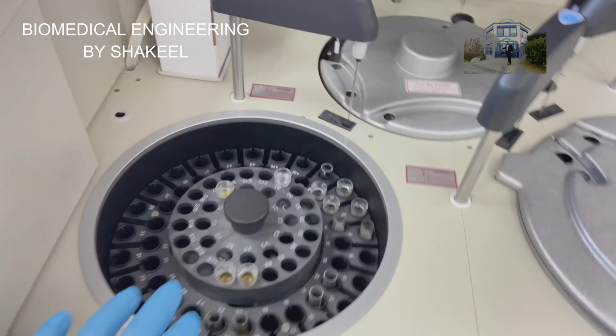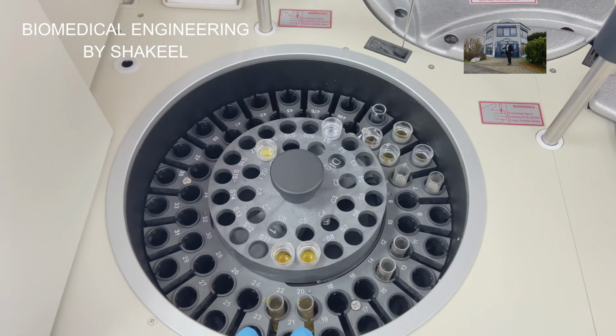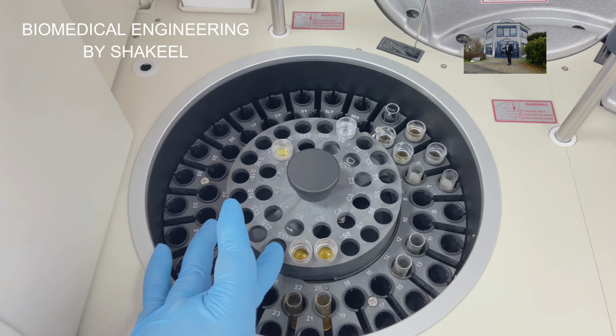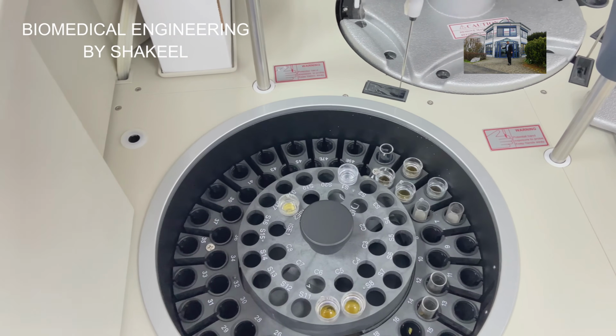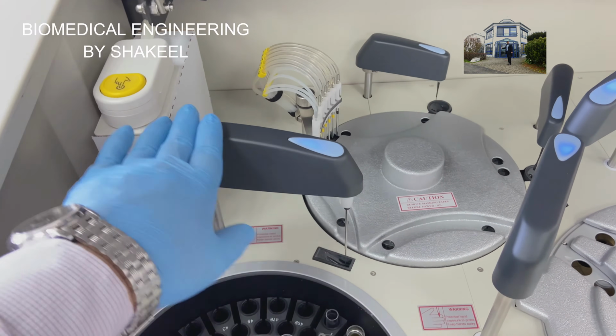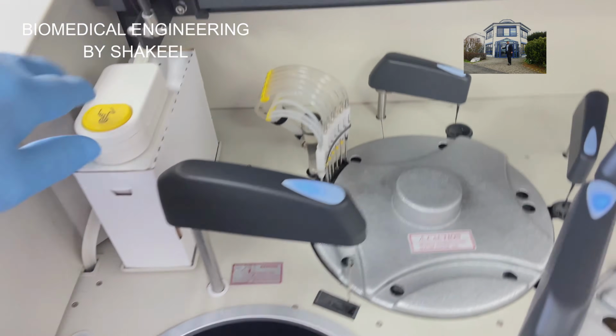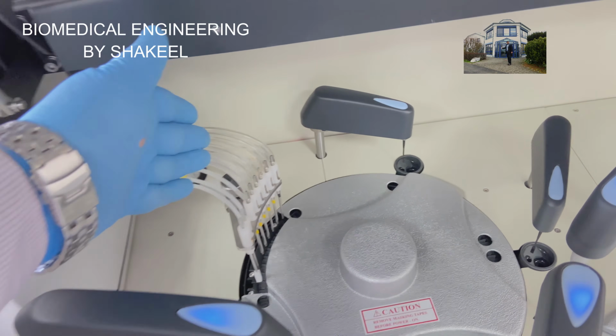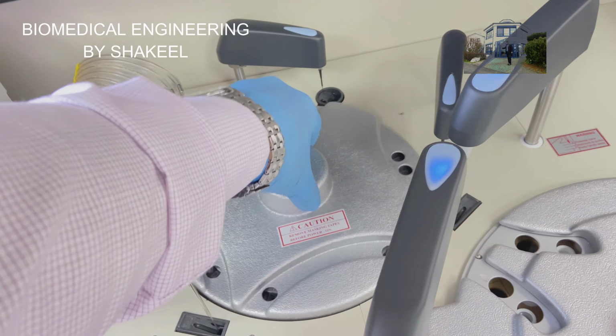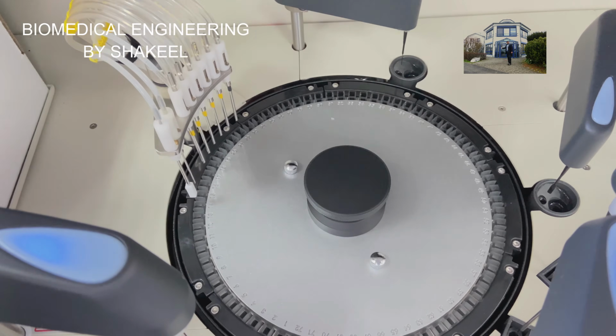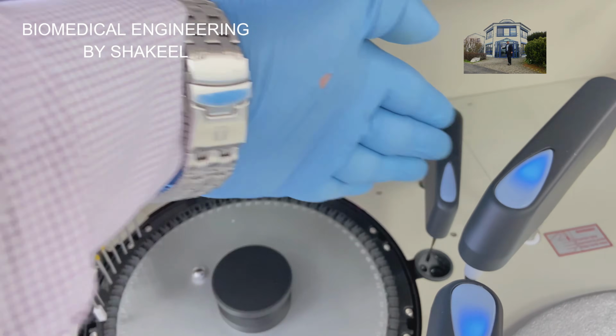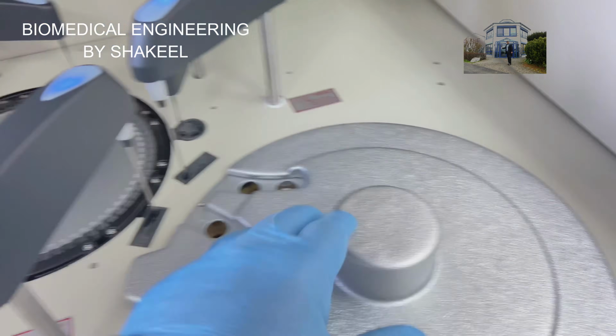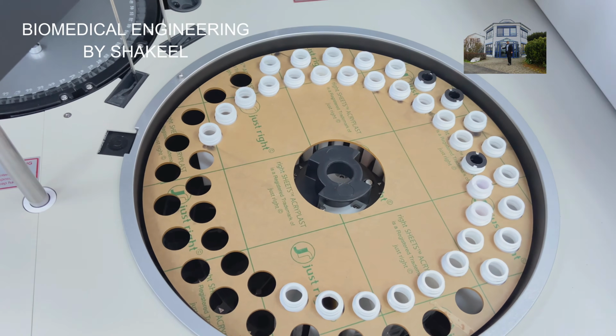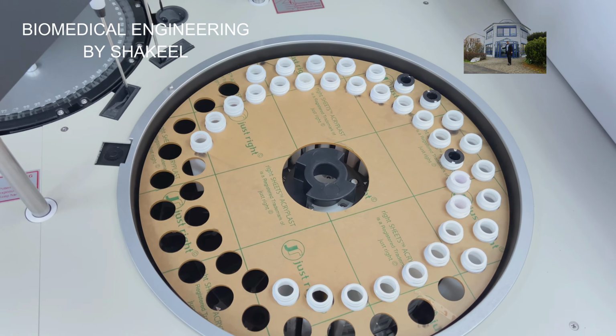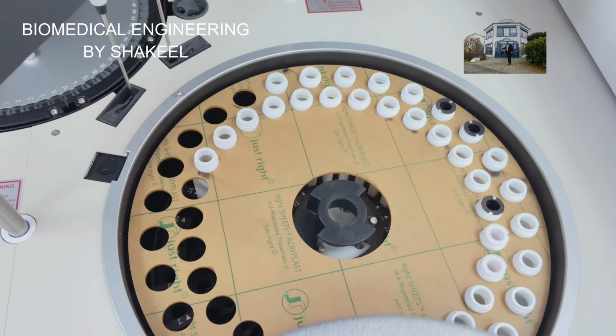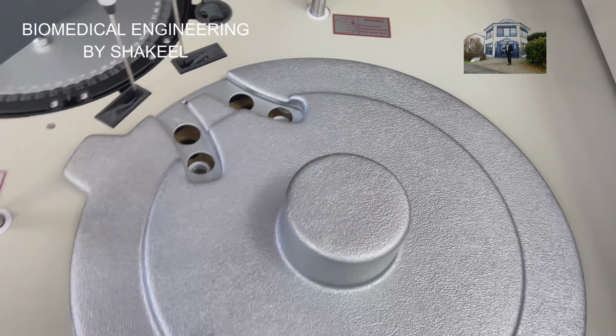Now about the modules. In the sample carousel we have outer 25 positions, inner 25 positions, outer 20 and inner 12. So total 82 positions for samples. Same as here we have the sample probe side, and this is for the ISE reagent, that's separate. This is the CRU unit, cuvette rinsing unit, and here we have 72 washable cuvettes. Let me show you. So these are the cuvettes, and stirrer 1, stirrer 2, we have the reagent 1, reagent 2, and here we have the reagent carousel. In the reagent side it has 56 positions. So 56 reagent positions are here, including the R1 and R2.